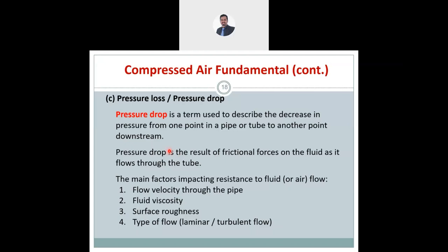There are a few factors influencing or causing the pressure drop. Mainly it is frictional force. Let's say your fluid is moving from one point to another. In between, because of the surface of the pipe, it can be because of surface roughness or your fluid viscosity. Let's say you are not using water, you are using oil, so the fluid viscosity will cause some frictional force. It's worse if you have a high viscosity fluid and also surface roughness. It will cause more frictional force, so it can cause a pressure drop.